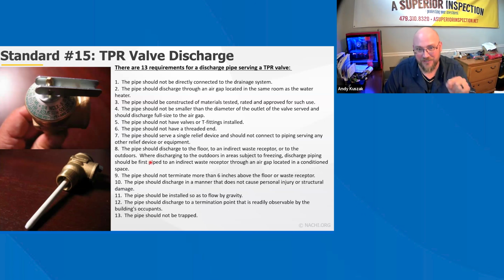That is generally how a plumber is going to find it, because a plumber has the tools and the knowledge and the experience to be able to replace that valve if they need to. I've seen valves where they ran through a wall but never exited the wall, or they go sub slab and then come out, and so much landscaping has been placed on top of it over the years that it's buried. Then the water at that pressure and temperature can't expel fast enough because it's being clogged by the landscaping outside. All of that backs up into the unit, and the tank can explode or rupture and cause interior water damage. I don't know if you guys have ever seen the video of a water heater exploding, but it is super impressive. I would definitely go to YouTube if you have an opportunity and look up water heater explosions, because it's very entertaining, and the damage that it can do to a house is shocking.